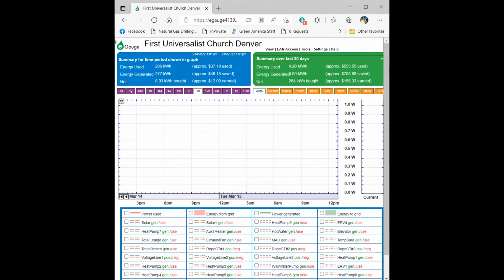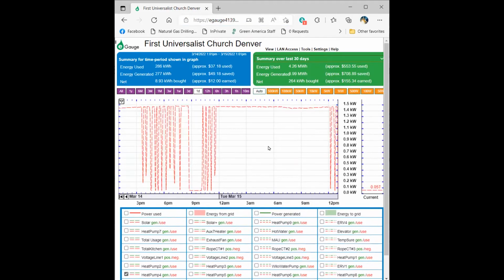What I'm going to do is activate the furnace that services the office area. It's referred to as heat pump number 4. And you can see it cycles on and off, on and off. However, during the day, if the temperature outside is more than, say, 20 degrees from the set temperature that you're trying to achieve, this 2-ton rated furnace is undersized, and it just stays on until, well, eventually it catches up and then can recycle.